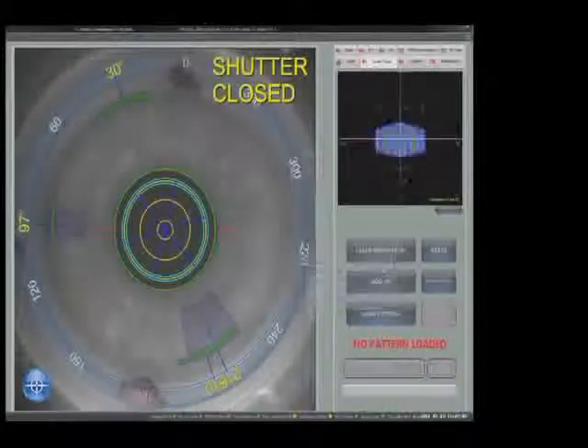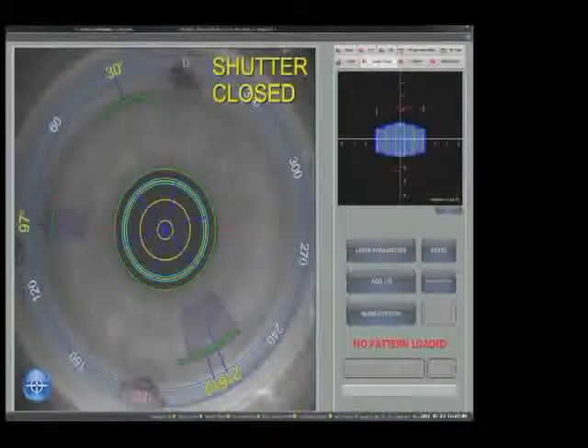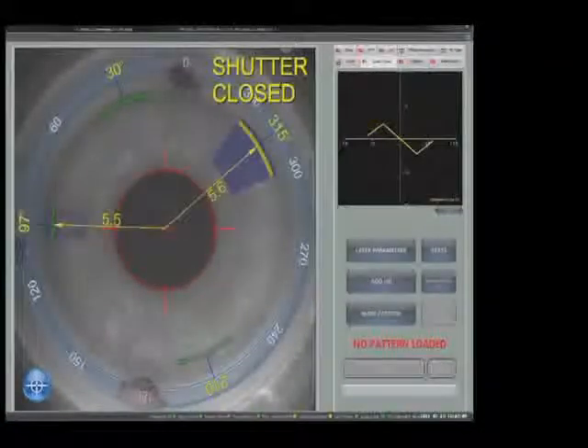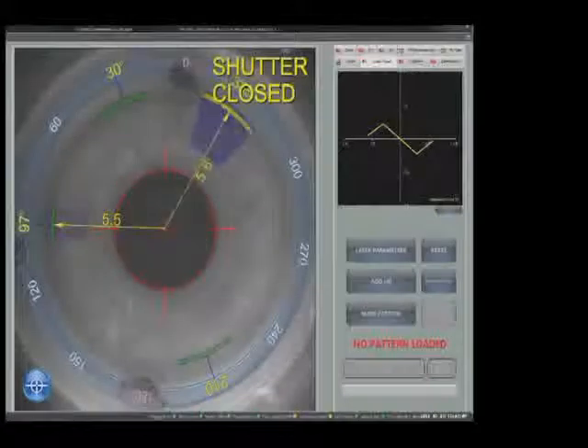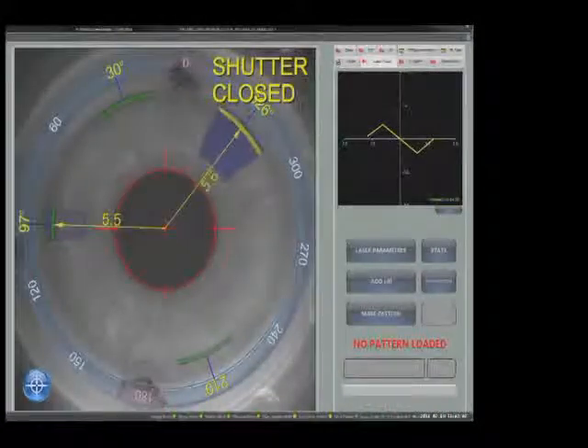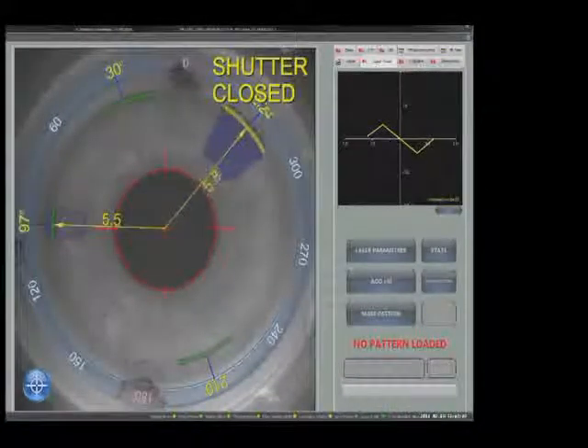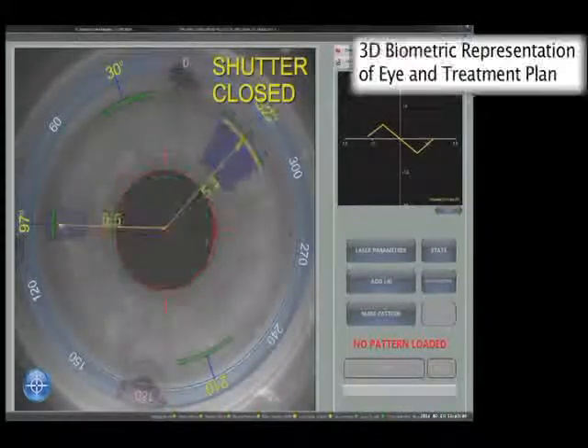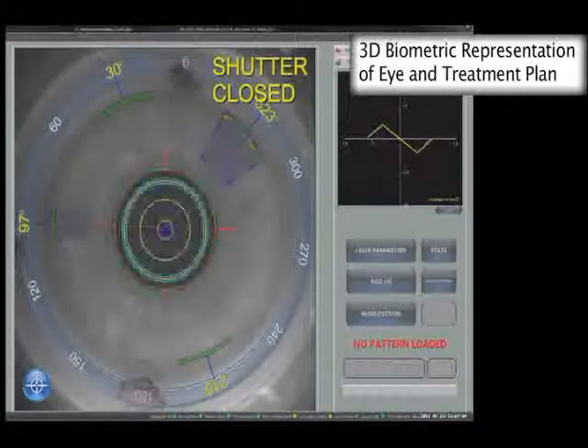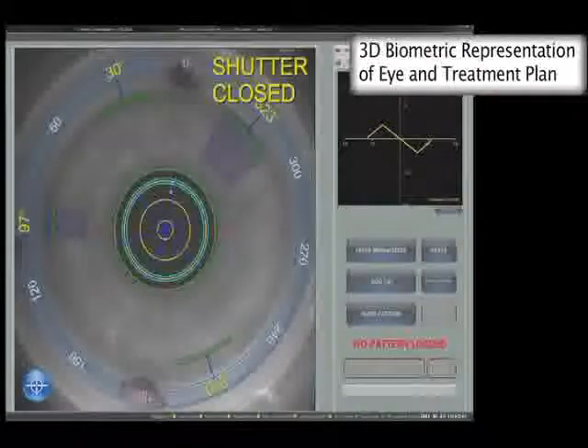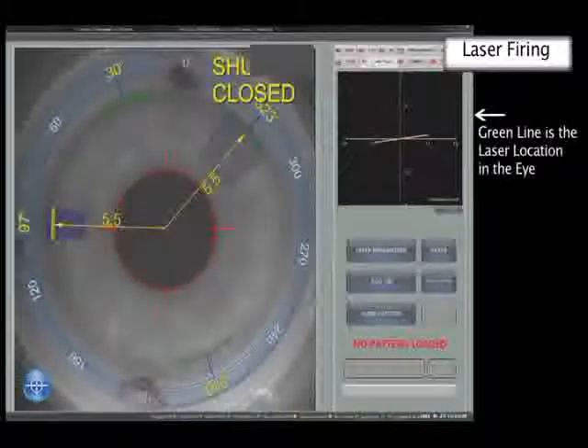The surgical incisions can be moved to avoid the LRIs and can be moved to ensure they are as far out towards the limbus as the imaged cornea allows. When the diameter of the LRIs is manually changed, the dimensions of the incisions are automatically adjusted to maintain a constant arc length.